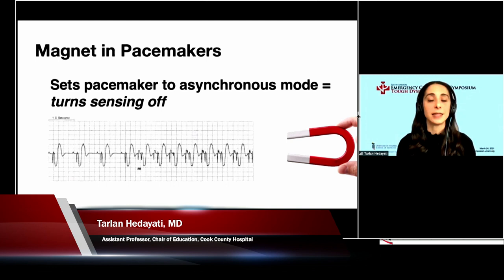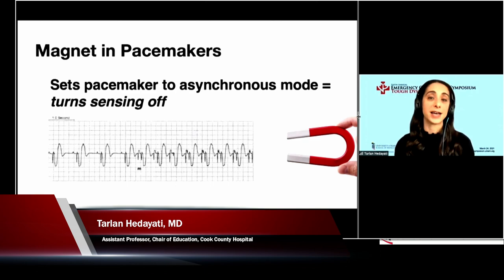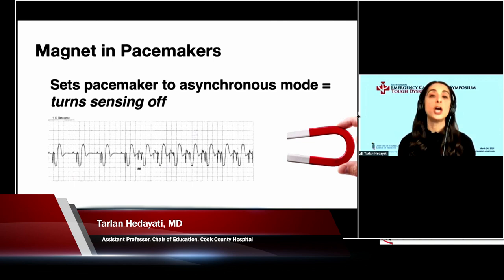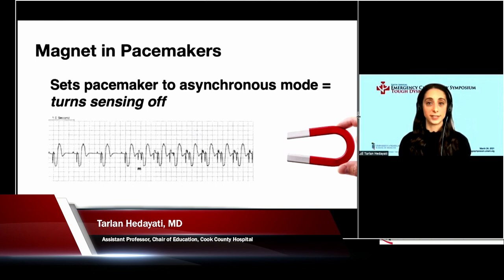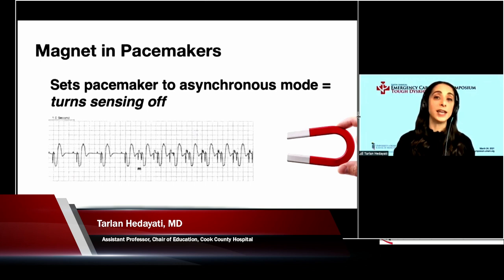I just want that pacemaker back online working again. So by putting that magnet on and turning the sensing function off, I am firing up the pacemaker to just go ahead and start pacing. It's not looking for anything, it's just going to pace. So in a patient with failure to pace, your solution is going to be your magnet.